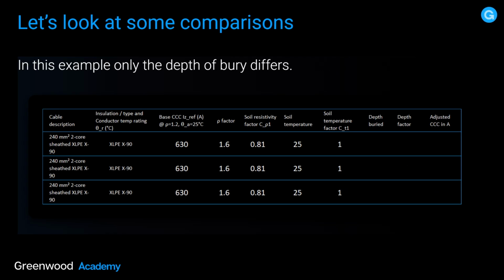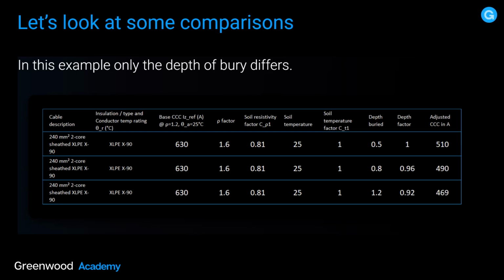Let's look at another example where the depth of bury differs. So we're starting off with a thermal resistivity factor of 1.6. We've got the same temperature across the board, 25, 25, 25, right? Depth of bury 0.5, depth factor 1, so we got 510. We're not going to bury at 0.5, but I just want to show you how the depth of bury determines, all other things being equal, the current carrying capacity of the cable. Let's look at the next example. 0.8, 490 as we saw before. If we go down to 1.2, you can see there's a drop from 490 down to 469. That's a drop of 21 amps because we've buried it from 0.8 to 1.2 meters. So you can see that correlation there.